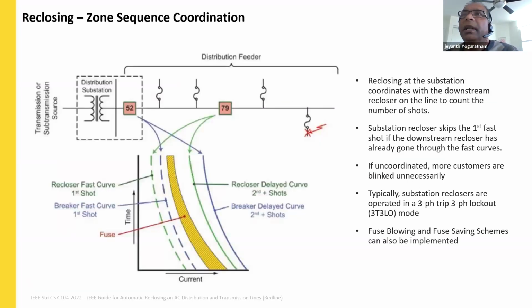Let's talk a little bit about reclosing. We all know the reclosing operation. Reclosing is typically used in the distribution system, where the faults are often temporary. Faults can be caused by weather, animals or vegetation. When there is a fault, the recloser will trip and isolate the fault area. But the next moment, the fault may get cleared, and then the recloser will close and reestablish power back to the users. If there is a permanent fault, it will time out, complete the whole sequence of reclosing operations, and finally go to the lockout mode.